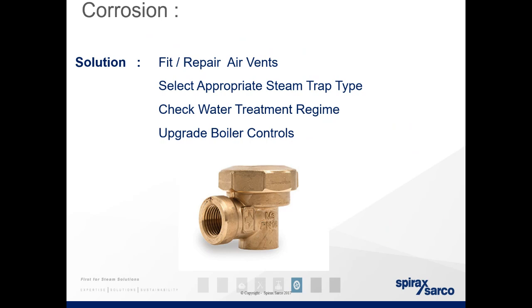Another indication of failing traps would be excessive flash steam from risers leading out of the building or the top of the feed tank. So all of these will indicate there's a challenge in your steam system. As soon as you get leaks, if they're not dealt with, they will cause more erosion and corrosion. Hopefully that answers your question. Anything else?